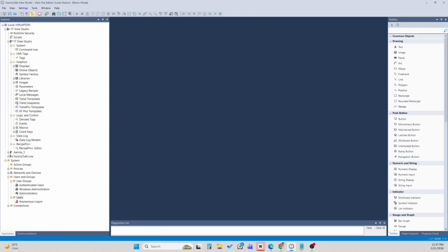This allows you to add a large number of existing Windows users and groups directly to the FactoryTalk system. However, there is one important risk. If all Windows user groups with administrative permissions are removed on the IT side, the operator will lose administrative access to the FactoryTalk directory. If this is a concern, you should create at least one FactoryTalk administrator account as a backup.